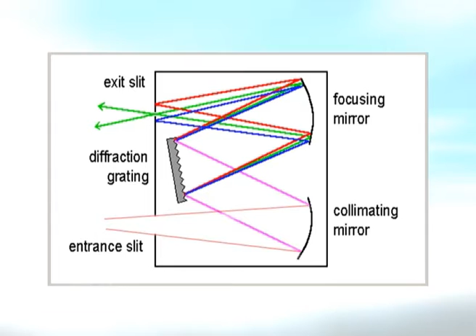Monochromators are generally composed of prisms and slits. Most of the spectrophotometers are double beam spectrophotometers. The radiation emitted from the primary source is dispersed with the help of rotating prisms. The various wavelengths of the light source, which are separated by the prism, are then selected by the slits, such that the rotation of the prism results in a series of continuously increasing wavelengths to pass through the slits for recording purpose. The beam selected by the slit is monochromatic and further divided into two beams with the help of another prism.